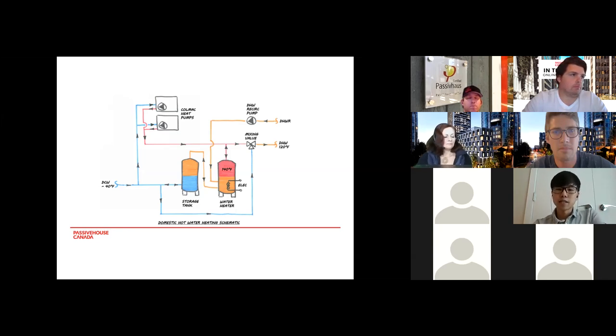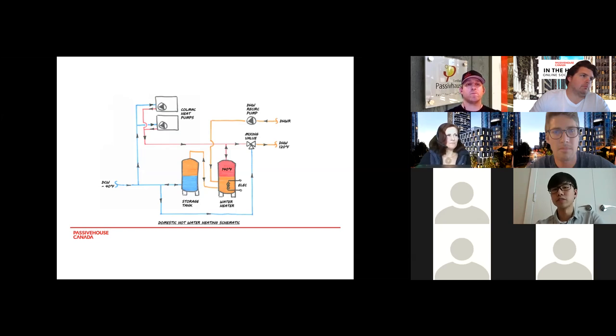We had a temperature immersion sensor located in the first storage tank that controls the two pumps integral to the Colmec units. Whenever the sensor detects the water temperature drop to around 130 degrees Fahrenheit, the Colmec heat pumps energize and start cycling water through the system, stopping when the temperature reaches 140 degrees Fahrenheit, where we ensure all Legionella is killed in the system.